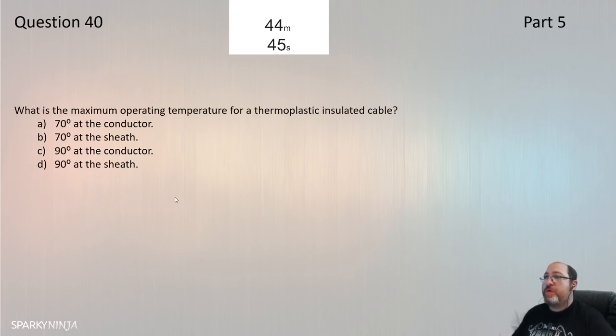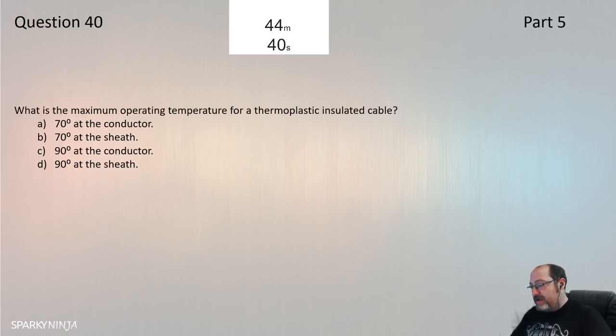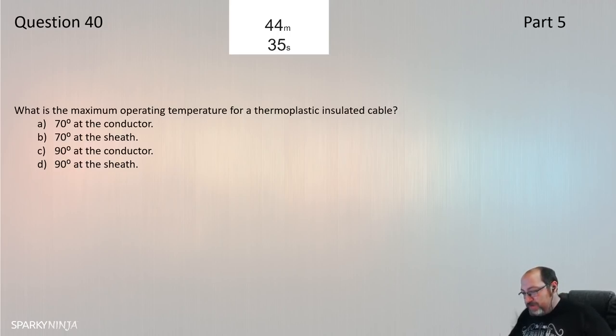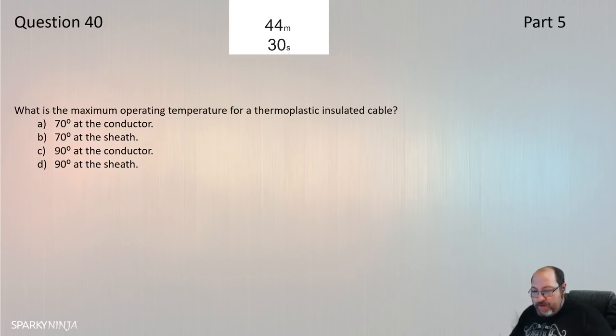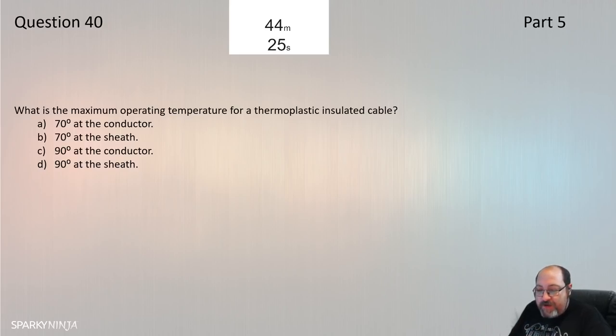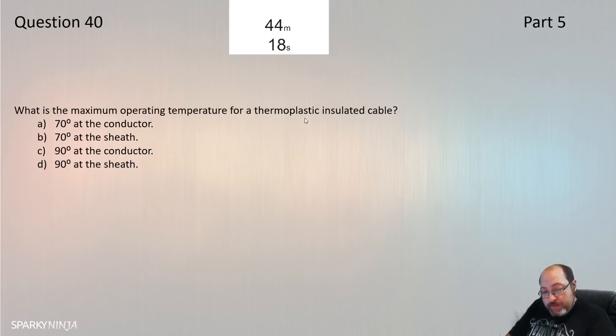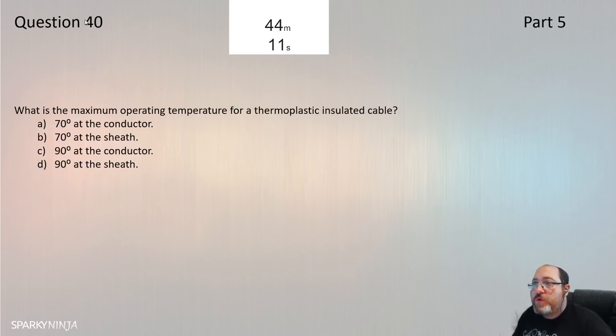Question 40: What is the maximum operating temperature of a thermoplastic insulated cable? This relates to Chapter 52 — selection of wiring systems — Table 52.1: maximum operating temperatures for cable types. For thermoplastic insulated cable, maximum operating temperature is 70°C at the conductor. Question 40 is A — 70°C.